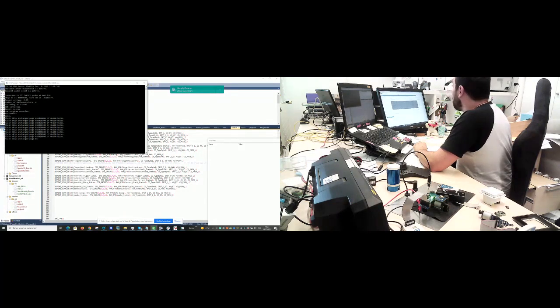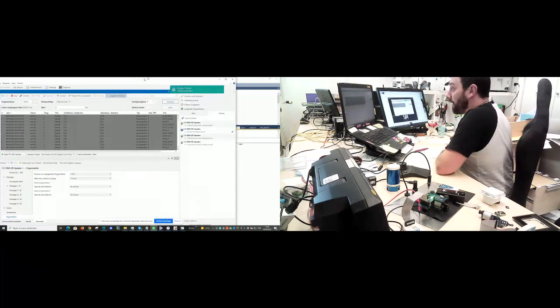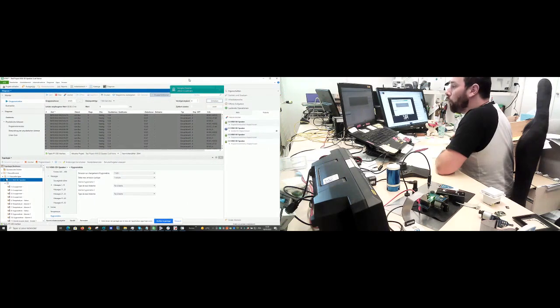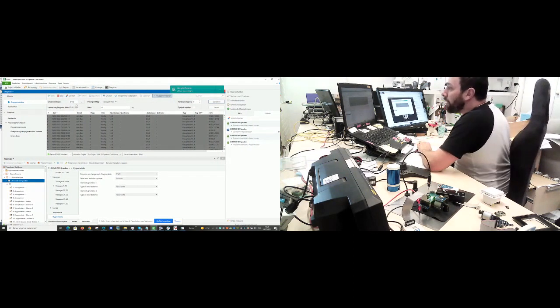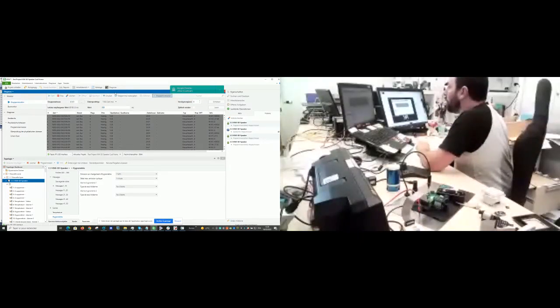The ETS is a standard software for putting the parameters and communication objects into a KNX device. And here we have a tool called monitor, so you can give an address for TP2, while the address for the motor drive, the data point type was 5 or 7.2, don't remember, and here we put a value, for example, and then we will send it.